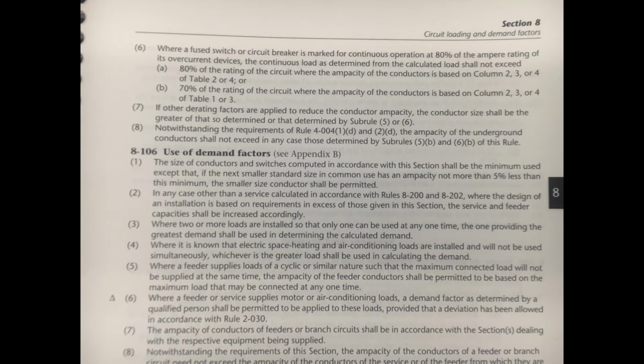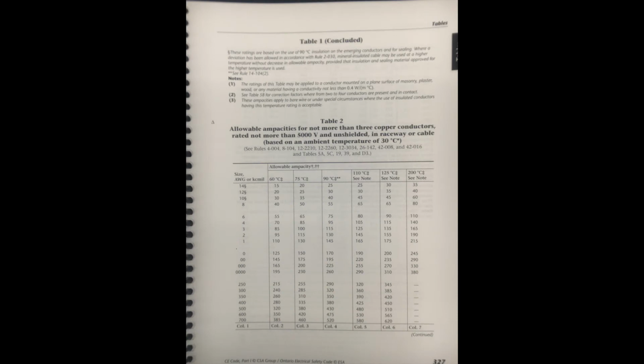Also looking here at 8-104 section 6, it says, when a circuit breaker is marked for continuous operation at 80%, then the load should not exceed this 80% rating. And looking at this chart in Appendix B, Table 2 applies to us, and it says that for our 14 gauge cable at 90 degrees C, our maximum ampacity is 25 amps. Putting it all together, it turns out our 14 gauge cable can handle higher ampacity than our circuit breaker at 15 amps. So the code states whichever is less is our maximum recommended circuit load.